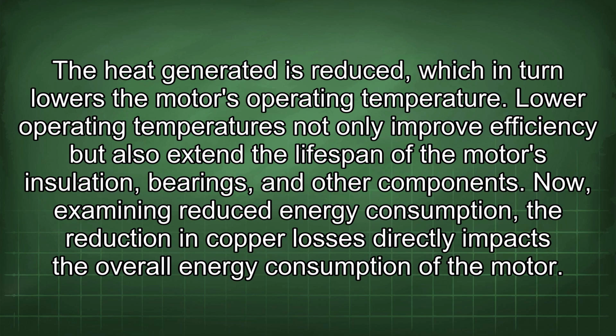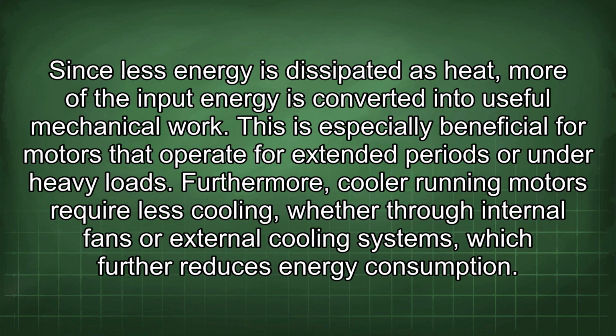Now examining reduced energy consumption. The reduction in copper losses directly impacts the overall energy consumption of the motor. Since less energy is dissipated as heat, more of the input energy is converted into useful mechanical work. This is especially beneficial for motors that operate for extended periods or under heavy loads. Furthermore, cooler running motors require less cooling, whether through internal fans or external cooling systems, which further reduces energy consumption.